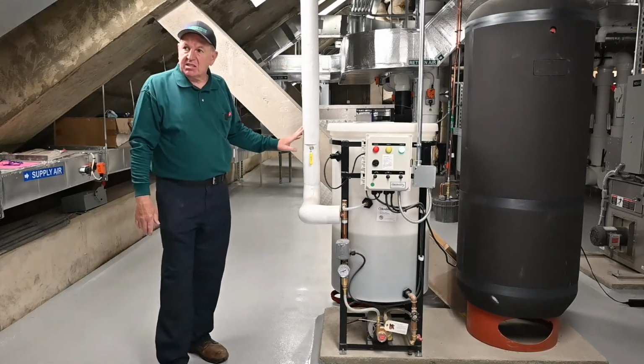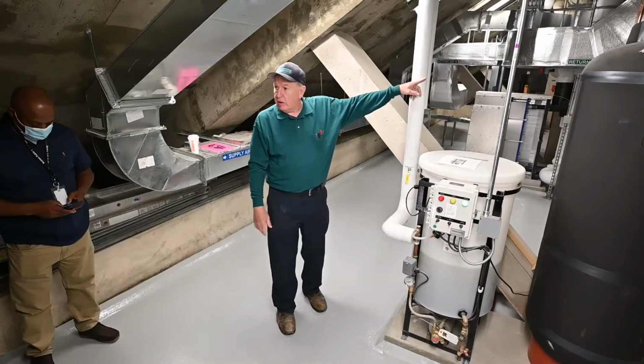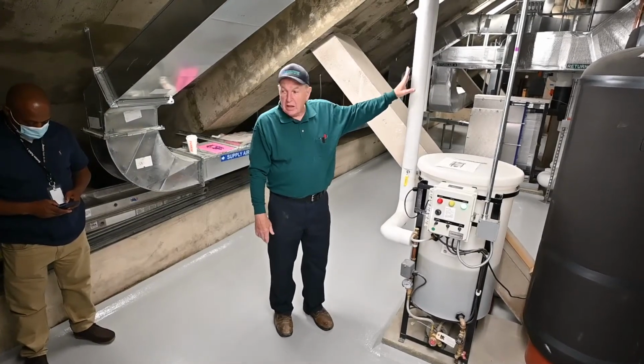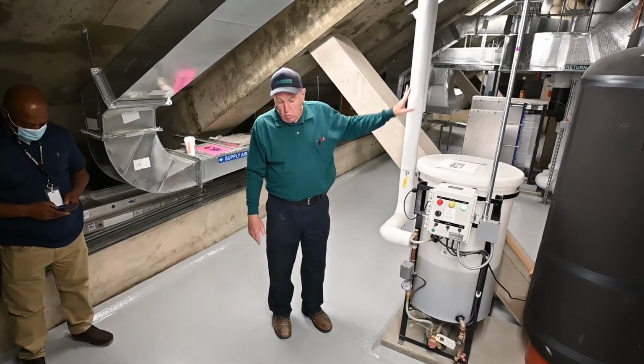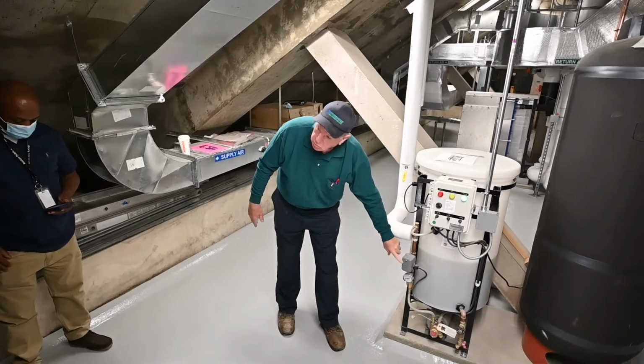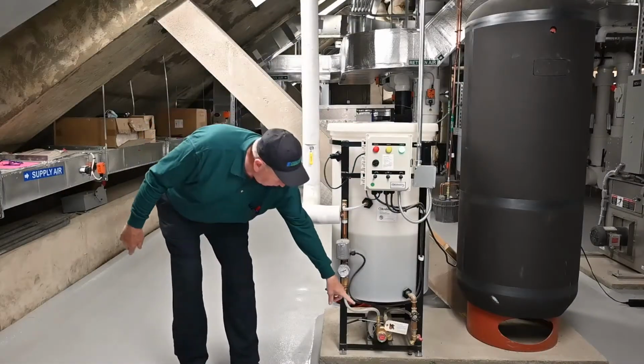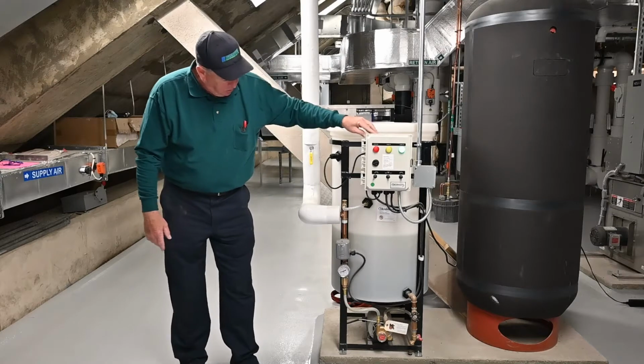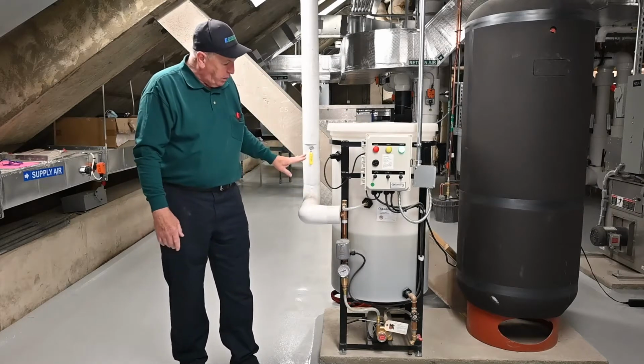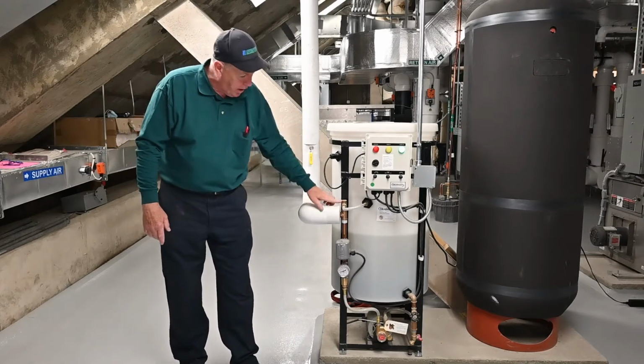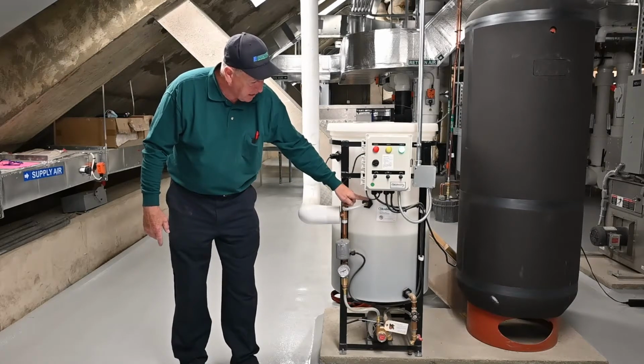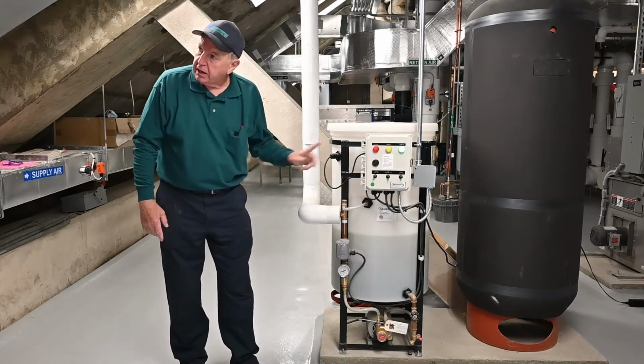This is the connection to the air separator on the pumps. Whenever that pressure gets too low, this pressure switch will sense it and turn on that pump. If for some reason the pressure gets too high, this relief valve will dump it back in. It'll race the fluid.